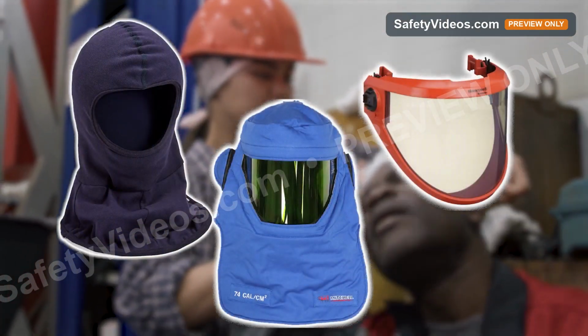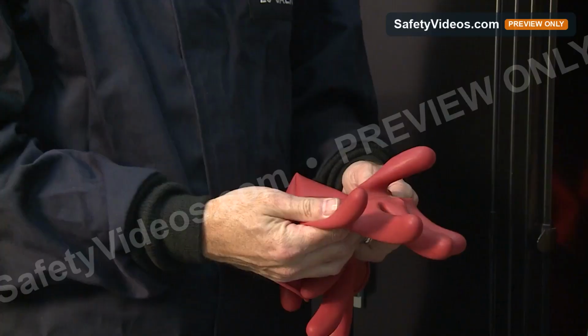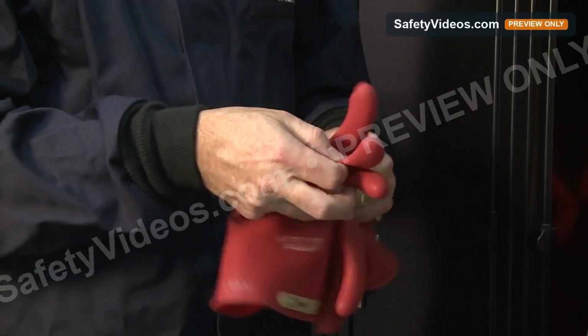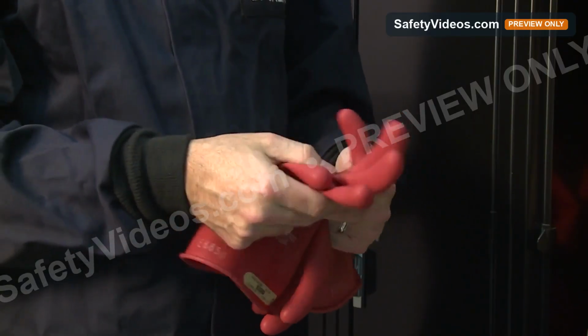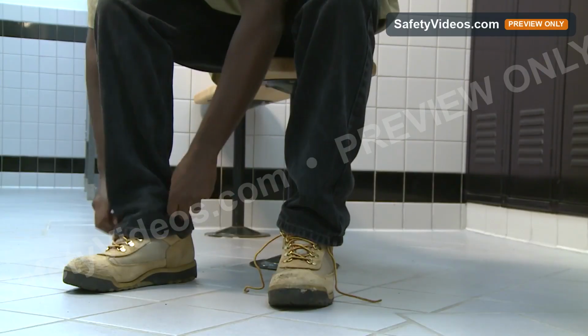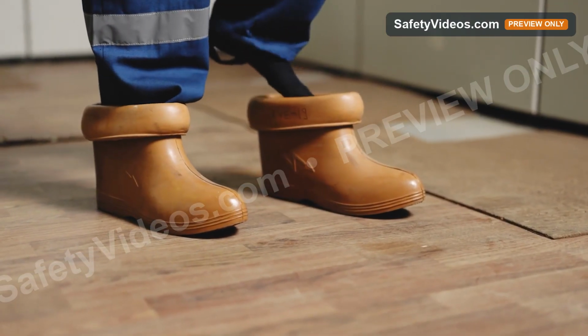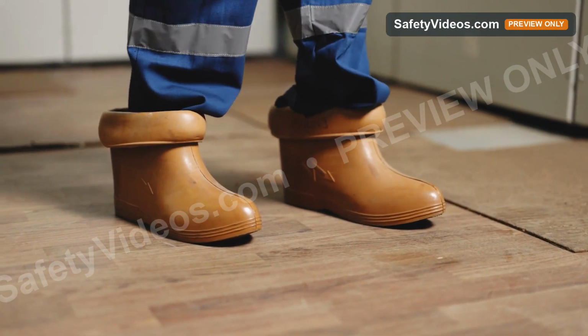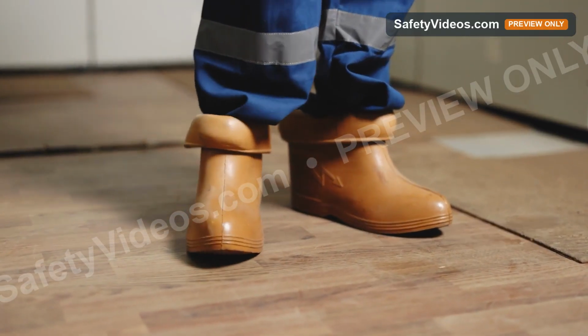When there is danger of a head injury, you should wear an arc-rated hood, balaclava, or a face shield. You can protect your arms and hands with rubber-insulated gloves and sleeves with built-in protectors. And don't forget about your feet. Insulated or leather footwear can provide protection against electric shock and arc flash events.